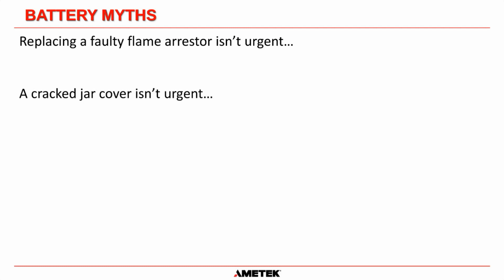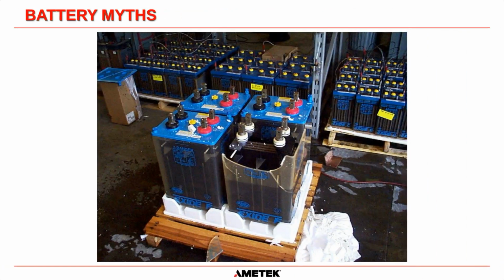And now we'll go into battery myths. Replacing a faulty flame arrestor isn't urgent, or a cracked jar cover isn't urgent. Well, I beg to differ, because we've seen the picture of what happens, okay? If you have a cracked jar cover and there is hydrogen escaping out into the world, if somebody causes an electrostatic discharge on that jar and there is hydrogen available and there is a crack, not only will the hydrogen outside the cell combust, it will then get down through the crack of the battery into the space that has a huge amount of hydrogen, and you've just caused a bomb. Okay? And it will do this. It will blow that battery to pieces.